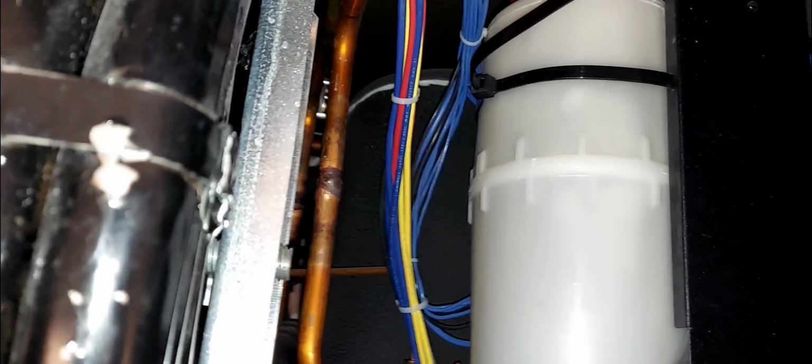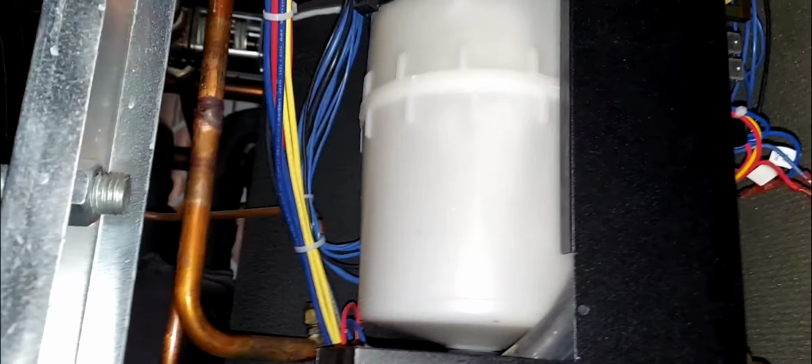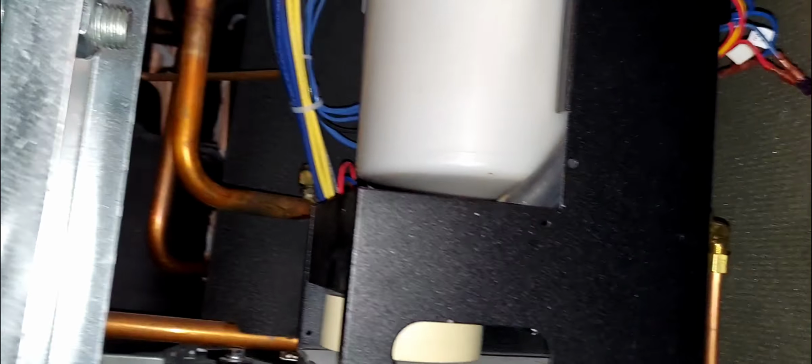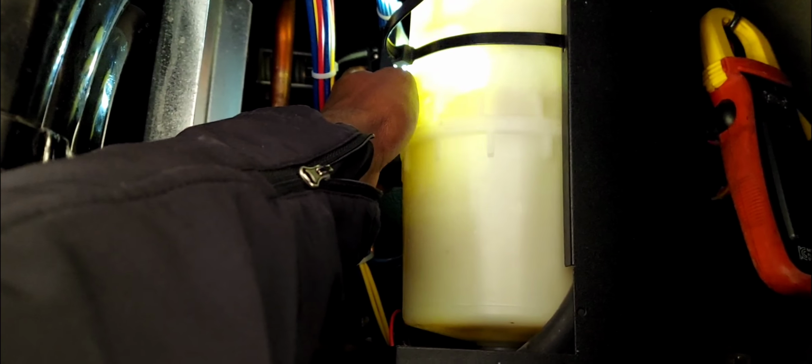That creates steam. When it boils, it's steam. Let's see right here. Look at my clamp draw on the humidifier. Just want to show you what's going on in the canister. Clearly you can see that your water is boiling.